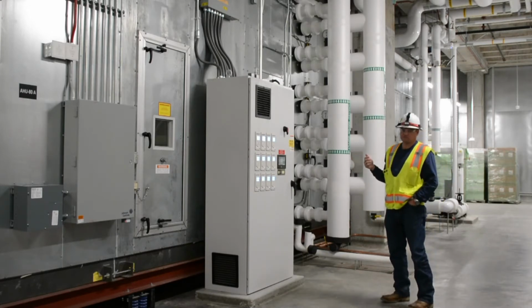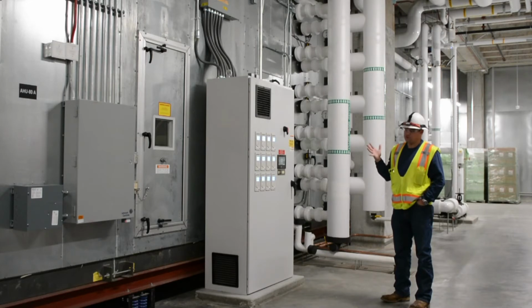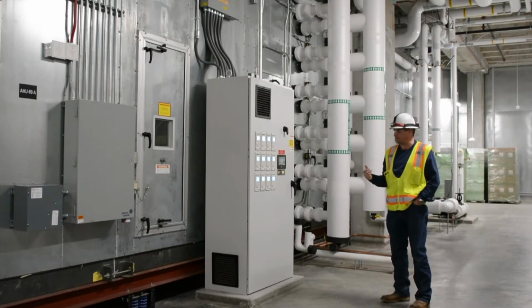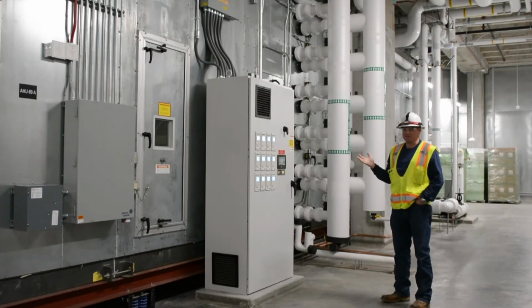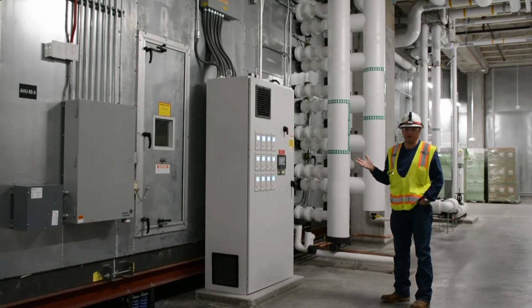Imbalance can also be an issue, so just ensure that when you do your maintenance, manually start each fan up and just listen for unusual noises or vibrations or anything of that magnitude, so that you can tell if there could potentially be a problem that needs to be corrected.